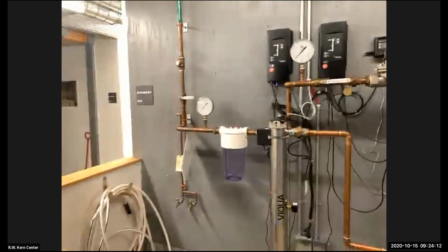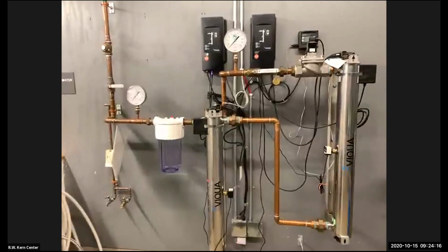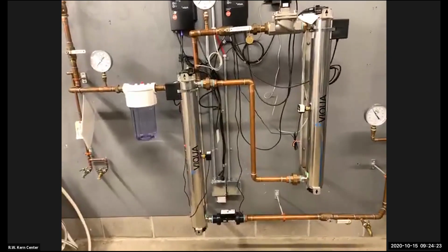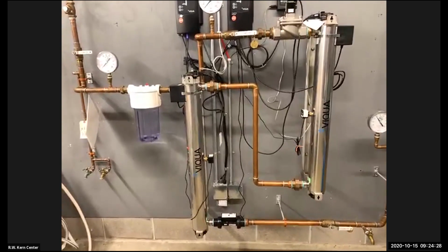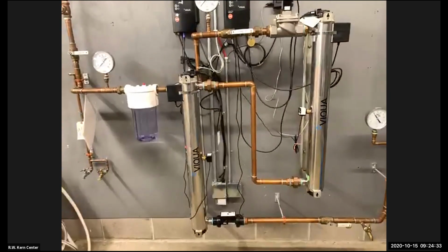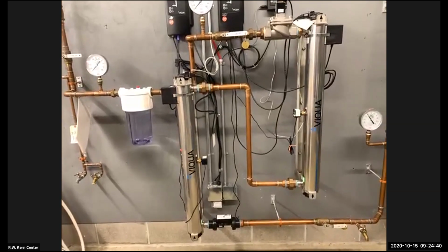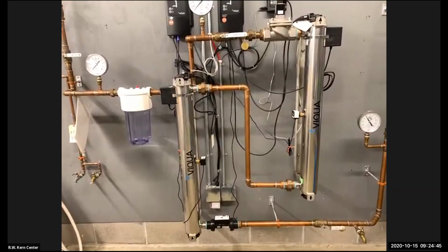And so there's a question about the alarms. As I mentioned, the alarm on the UV shuts the water off. So there's an ability to monitor that alarm, but it actually turns the water off when there's a problem. Most of these are audible alarms that scream, and Sarah can hear them from her desk. And if there is a problem, she goes down and checks them. And because of the use of this building, there are also people looking in on things regularly. There's a building management system that also keeps an eye on things.